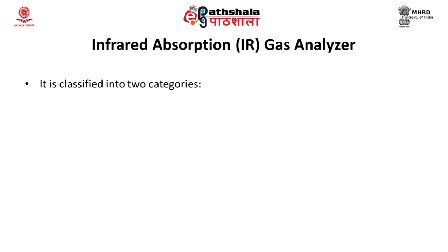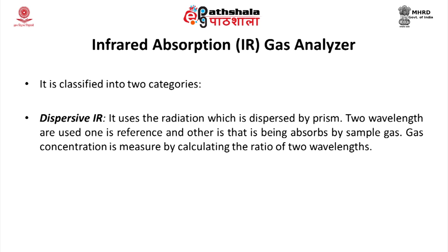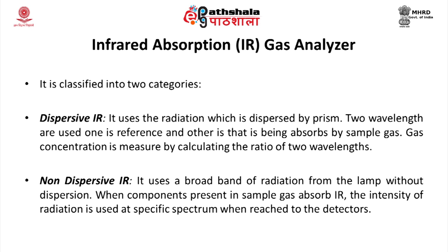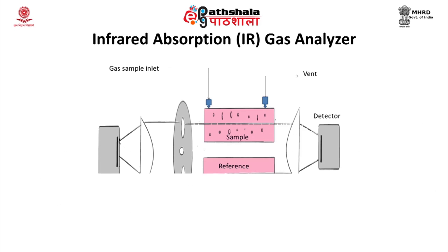IR analyzers are classified into two categories: dispersive IR and non-dispersive IR. Dispersive IR uses radiation dispersed by a prism; two wavelengths are used — one as reference and another absorbed by the sample gas — and gas concentration is measured by calculating the ratio of these two wavelengths. Non-dispersive IR uses a broad band of radiation from the lamp without dispersion. When a component in the sample gas absorbs IR, the intensity of radiation is reduced at a specific spectrum reaching the detector. Two detection methods are used: a gas detector and a solid-state IR detector.